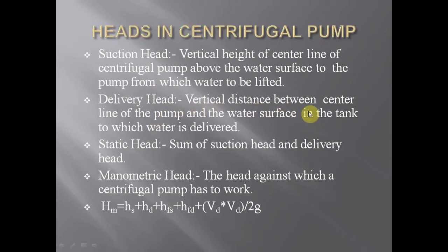Delivery head is the vertical distance between the center line of the pump and the water surface in the tank to which water is delivered. Static head is the sum of the suction head and delivery head. Manometric head is the head against which the centrifugal pump has to work, that is Hm equal to Hs plus Hd plus Hfs plus Hfd plus Vd squared divided by 2g.